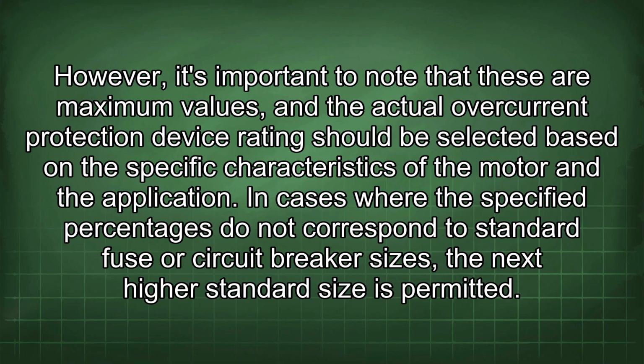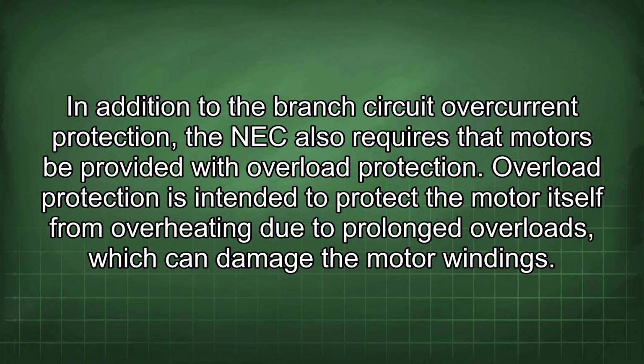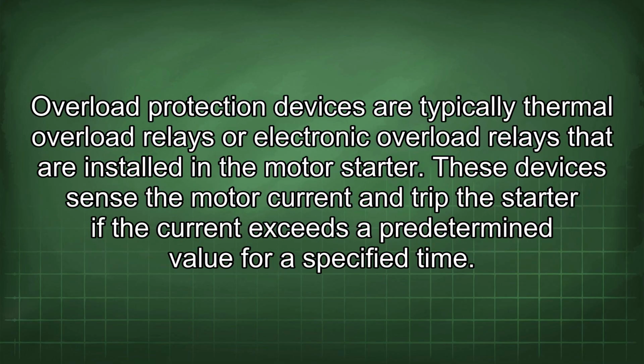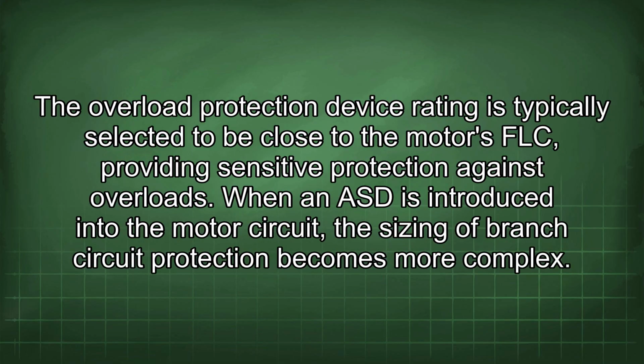In addition to the branch circuit overcurrent protection, the NEC also requires that motors be provided with overload protection. Overload protection is intended to protect the motor itself from overheating due to prolonged overloads, which can damage the motor windings. Overload protection devices are typically thermal overload relays or electronic overload relays that are installed in the motor starter. These devices sense the motor current and trip the starter if the current exceeds a predetermined value for a specified time. The overload protection device rating is typically selected to be close to the motor's FLC, providing sensitive protection against overloads.